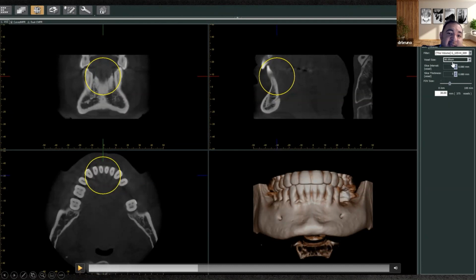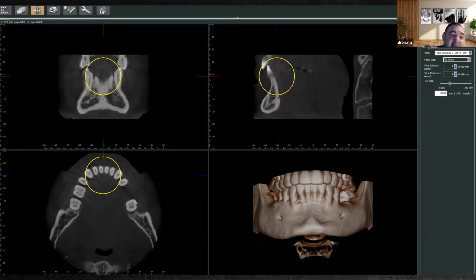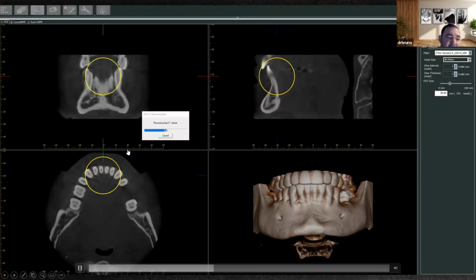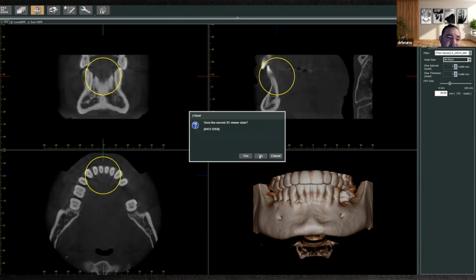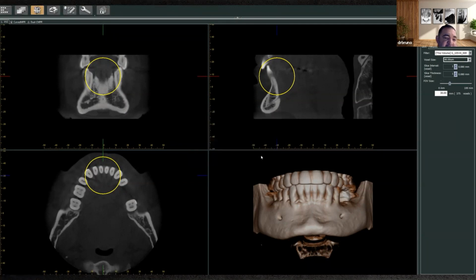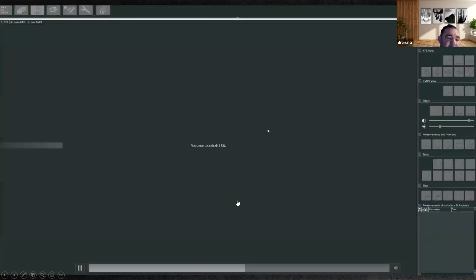So I selected the area, I selected my new voxel size, I selected now the smallest interval, the smallest thickness, and I hit run. What the computer is going to do is use the base images acquired for the large field of view and reconstruct a brand new volume just for that area of interest. It takes about 3 minutes for this process to work. I'm just speeding up the video here so you can see it's doing its processing. Say yes or no, up to you if you want to save this or not. And now it's going to open the new volume.